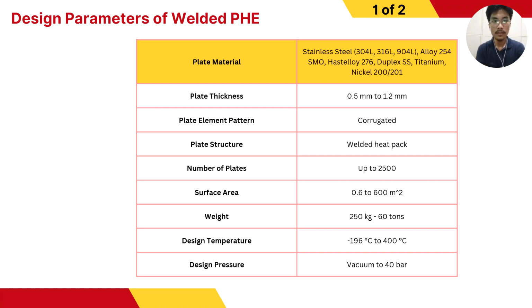Because of their strength and rigidity, these materials are very helpful on a welded plate heat exchanger, as they can survive varying temperatures and pressures. But we should also take note that the plate material must be carefully selected based on the working fluids, the working conditions, and the temperature and pressures where the welded PHE is going to be utilized. Because if not suitable, the plate material used can cause major problems and overall damage on the welded plates.